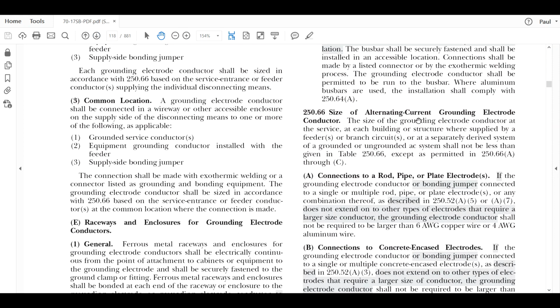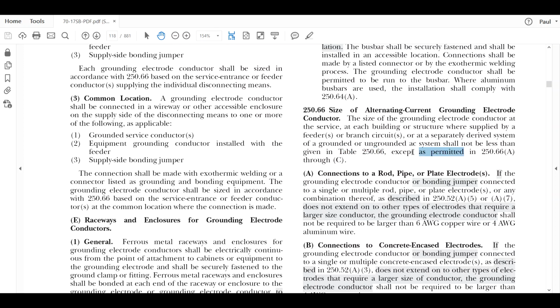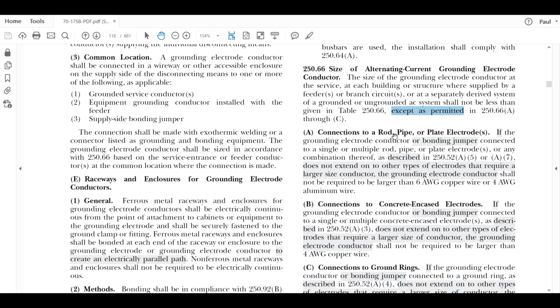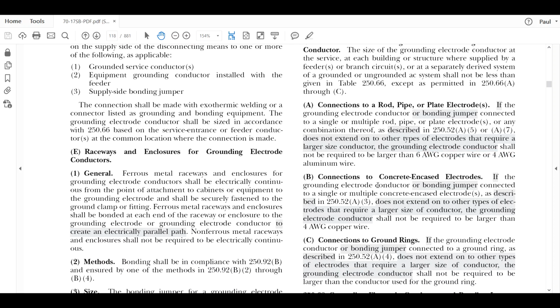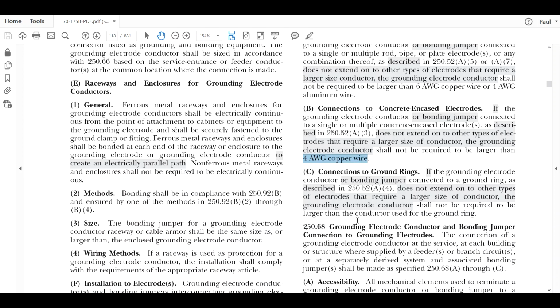Okay, so the general rule tells us to use the table. However, it says except as permitted, so it's a permissive rule. If your electrodes are rod, pipe, or plate, then the grounding electrode conductor doesn't have to be larger than a 6 copper or 4 aluminum. Okay. If it's a concrete encased electrode, then it doesn't have to be larger than a 4. Notice it doesn't give an aluminum allowance there.